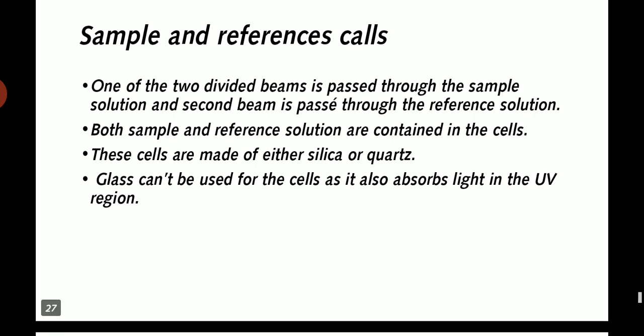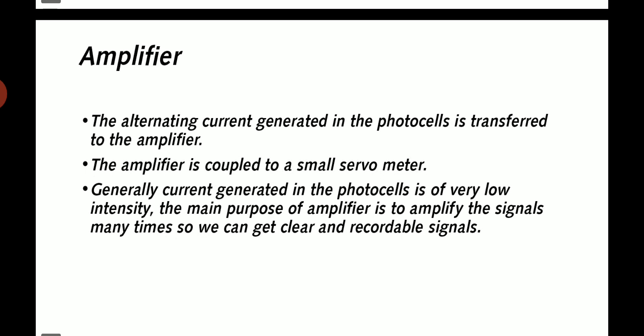Sample and reference cells. One of the two divided beams is passed through the sample solution and the second beam is passed through the reference solution. Both are contained in cells. These cells are made of silica or quartz. Glass cannot be used for the cell as it also absorbs light in the UV region.